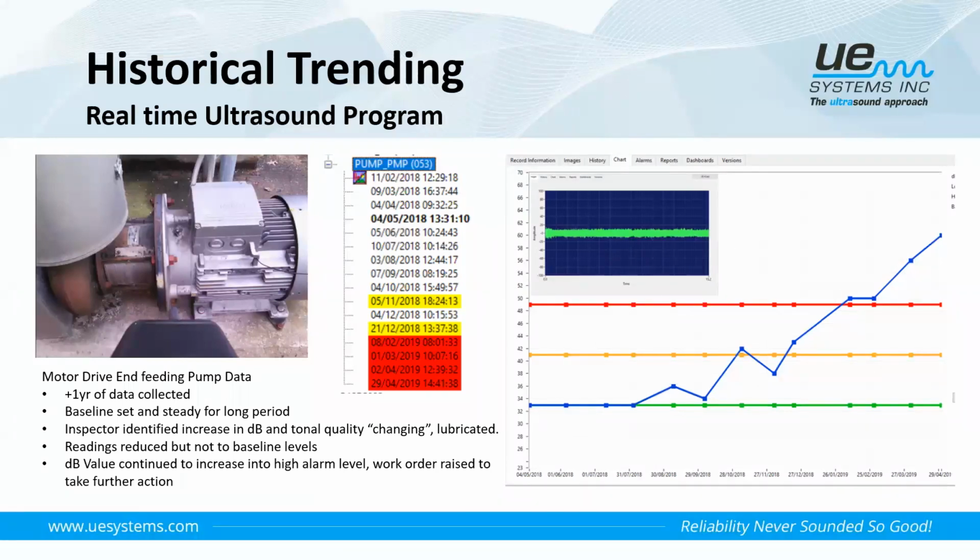We hit the low level alarm first of all, lubrication applied, but the sound does not return to the baseline, but does reduce slightly. But then after we've lubricated, the sound starts to increase again and carries on increasing, which tells us that it's not a lubrication related problem anymore, it is a physical problem actually occurring. So now the work orders need to be raised to take further action. But a great example again of how to use historical trending to help us with understanding the health of our assets.